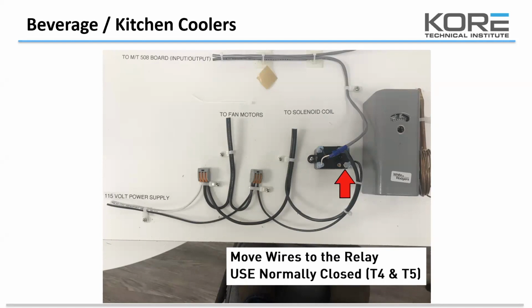We put a couple of female spades on them and connect that to 4 and 5, which are normally closed, so that we fail in refrigeration mode. This is one of the easier and simpler transformations that we got.